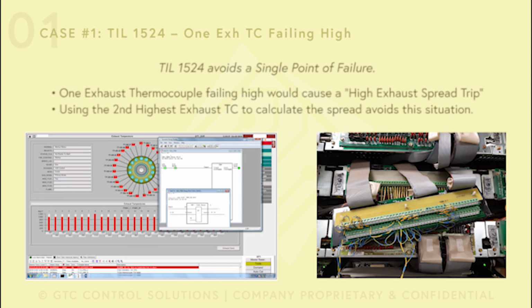You see that we also have created some sequencing there to enable testing without forcing signals that go everywhere. And what we did is we took a spare thermocouple terminal board, this is for a Mark V, and installed it with jumpers and with millivolt sources. You will need basically 2 millivolt sources to implement the testing. And once it's tested at your site, in your unit, you don't ever need to test that sequencing again. Once it proved that it's working, it'll work exactly the same always.